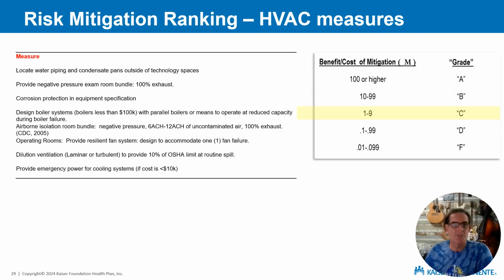So here are the mitigations that got a C. These are the ones where the order of magnitude of the investment and the order of magnitude of the benefit are right in the same ballpark. So you can't call these sound investments or good investments, but you also can't say that they're clearly poor investments. So I'll have you notice about 4th down on the list that designing boiler systems with parallel boilers, if the cost of the install is less than about $100,000, is at this level.